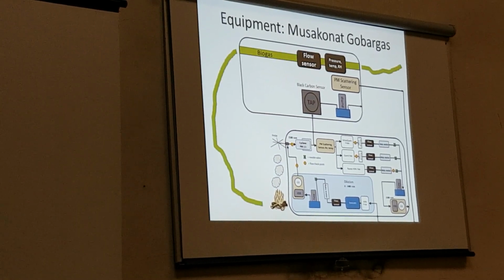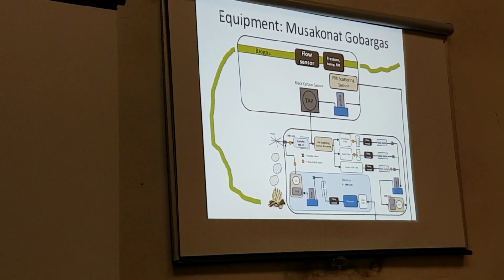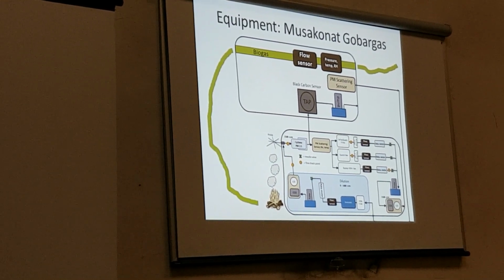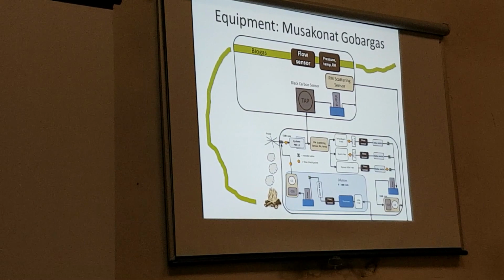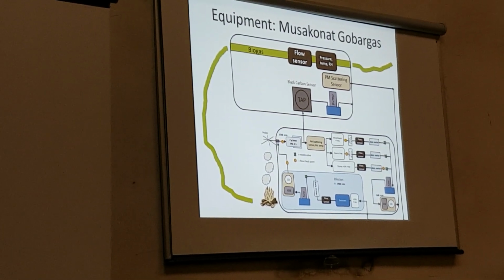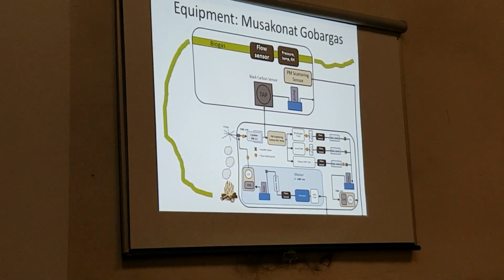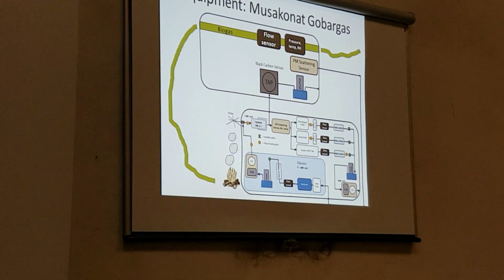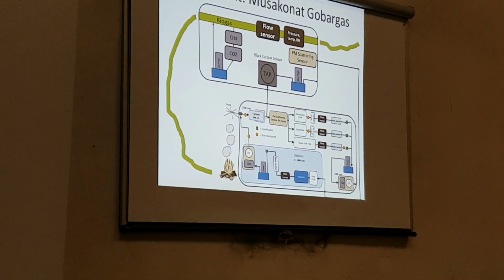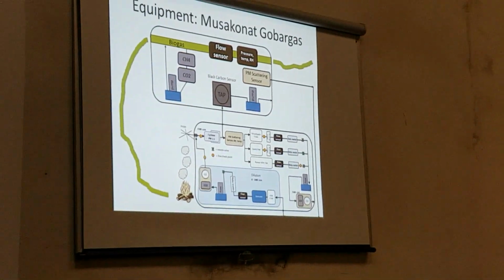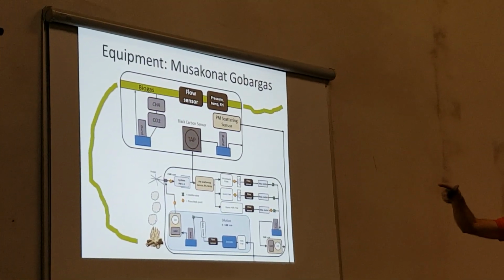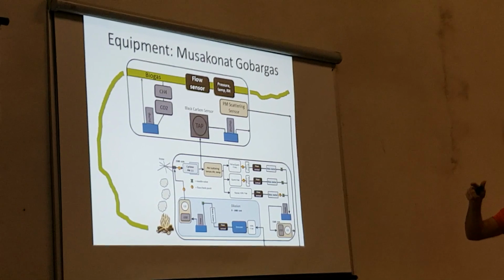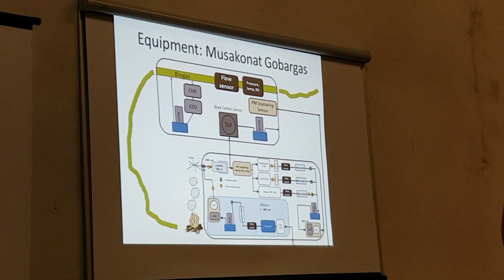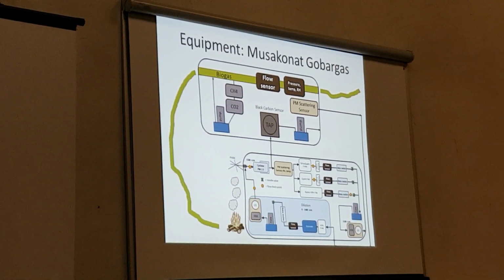We also need to be measuring the flow of biogas during the test, so we put the same sensors from that box into this box for the emission measurement. But we also need to measure the composition of the gas. For the carbon balance we need to know how much carbon is in the gas, but also the energy content. So we're measuring percent methane and percent carbon dioxide in the fuel, and we can calculate the remaining balance.